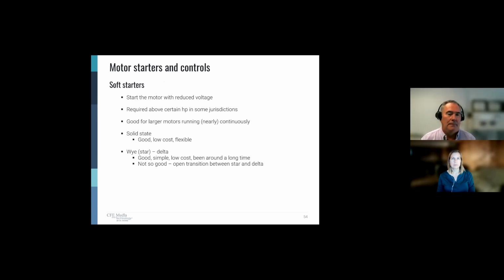So we get a little bigger motor, we got a little more of a problem. So they came up with something called a soft starter. Soft starter has been around a long time. Basically what it does is it starts the motor with reduced voltage and gets the motor to come up to speed in a little bit more of a controlled fashion. And then it switches up to full speed and takes off and runs. Again, these are good for larger motors running nearly continuously. Some authorities having jurisdiction will require them above a certain horsepower because they don't want that large shock back into the electrical distribution system.